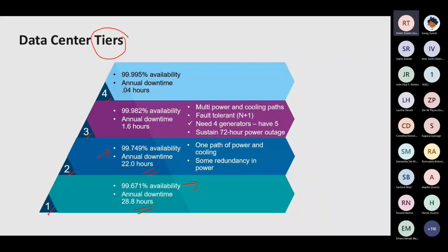It's called planned downtime. Now, when it comes to tier three, you will always have one additional piece of equipment available. That's called N plus one. For example, if you have 4 generators for your operation, 4 plus 1 will always be available. So one additional resource is available for providing a backup solution. And tier four is where your mission critical activity happens. So generally you'll have a 2N plus 1 kind of model used in a data center.